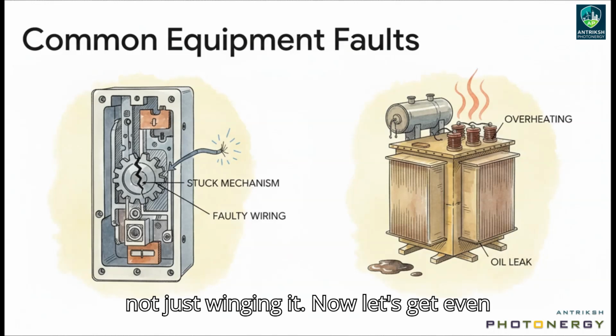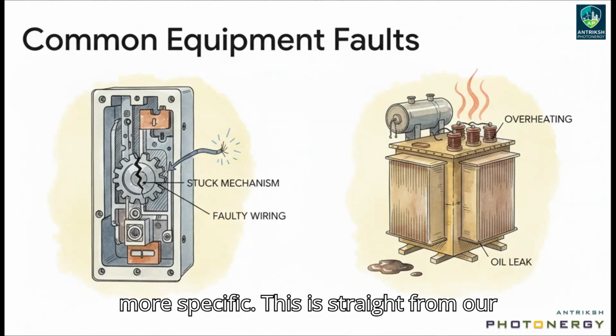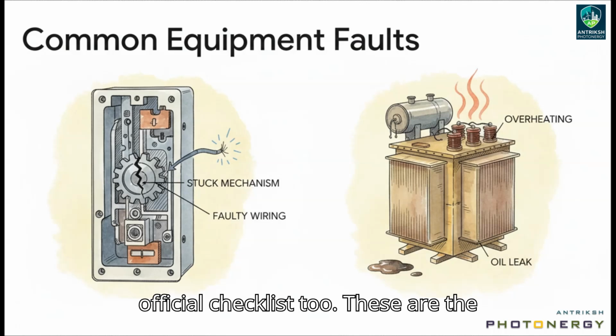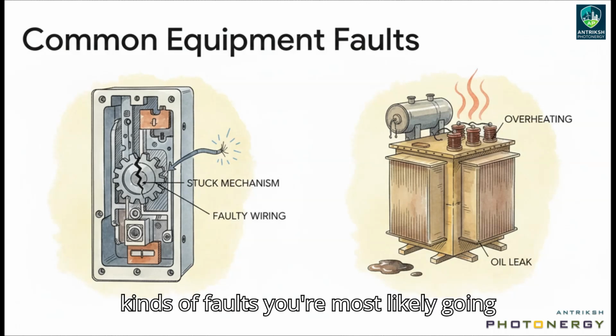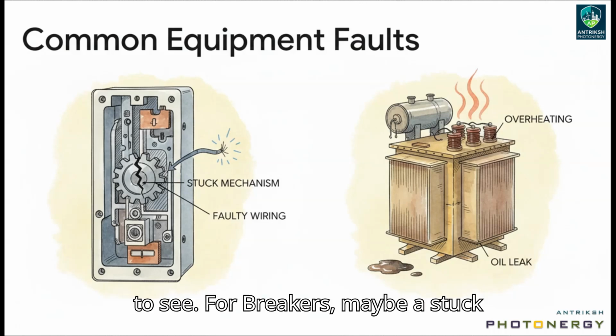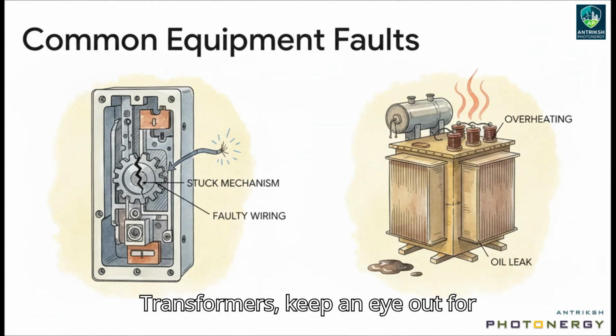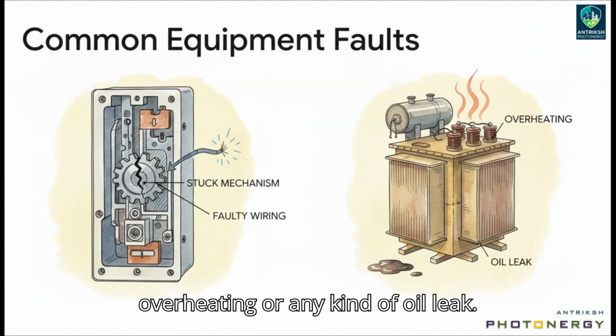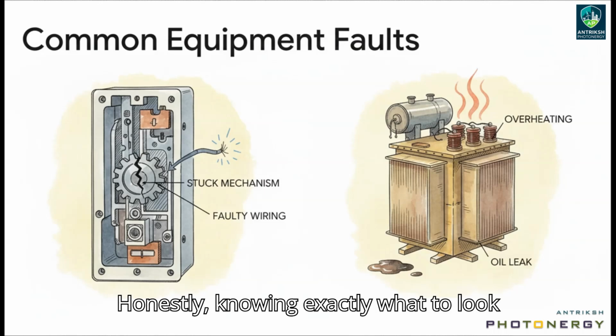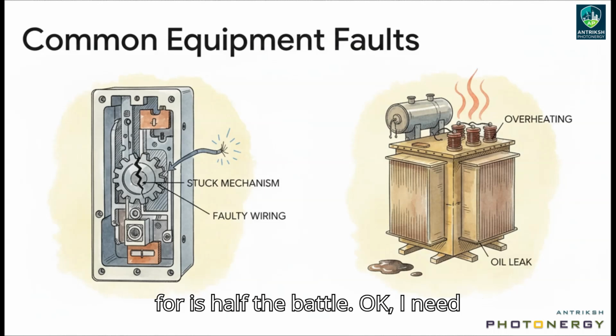Now let's get more specific, straight from our official checklist. These are the kinds of faults you're most likely to see. For breakers, maybe a stuck mechanism or bad signals. For transformers, keep an eye out for overheating or any kind of oil leak. Knowing exactly what to look for is half the battle.